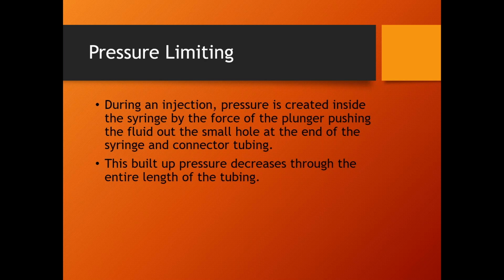Plus, 300 PSI in a patient's heart, and actually, that 300 PSI is for CT and MRI injectors. Angio injectors, the ones where they use a catheter, can get over 1,000 PSI, 1,000 or 1,200 PSI in some cases. No, of course we're not putting that in the patient. So how this works, and you have to kind of know your fluid dynamics a little bit: 300 PSI in my syringe here, when it gets up to this 1 millimeter wide opening at the top and goes into the connector tubing, which I'll show in a second, now we're down in the single digits of pressure. There's 300 PSI here, and there's literally like 3 PSI when it gets in here, okay? And it goes to the IV needle in the patient.